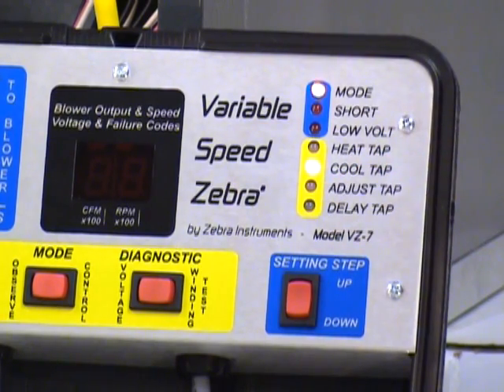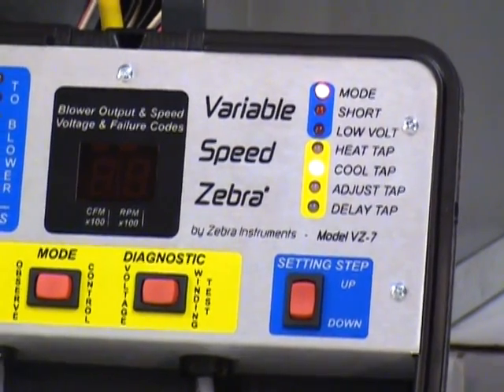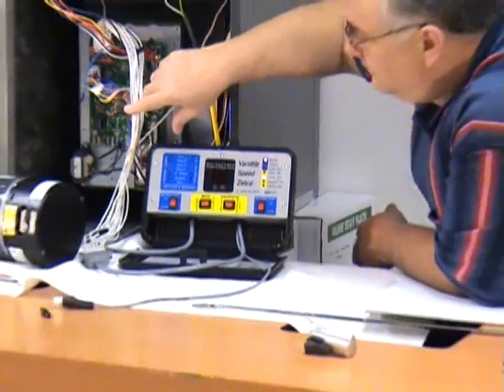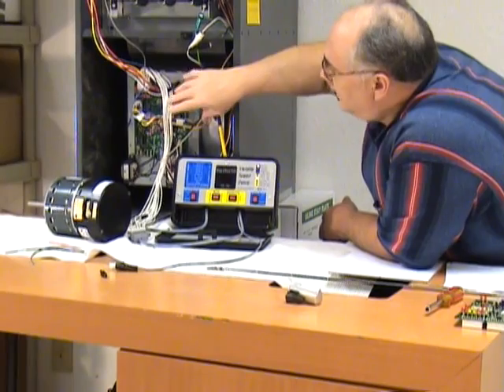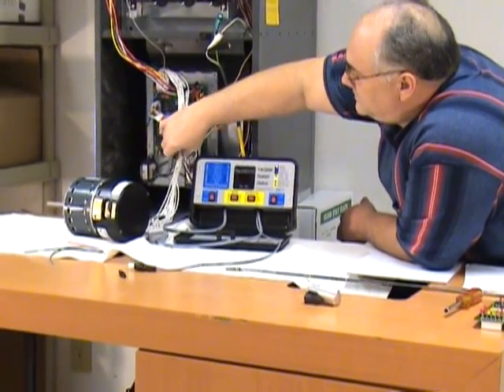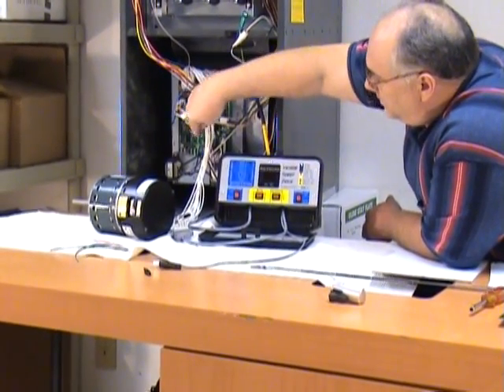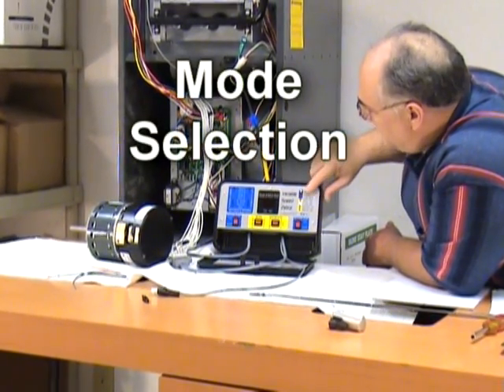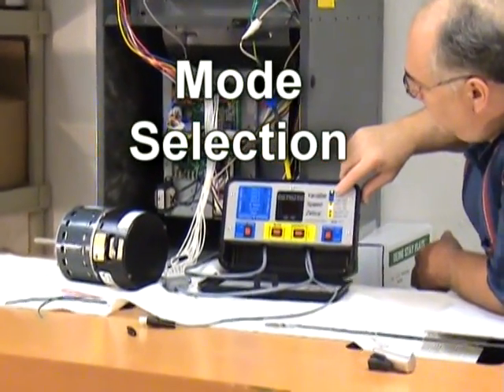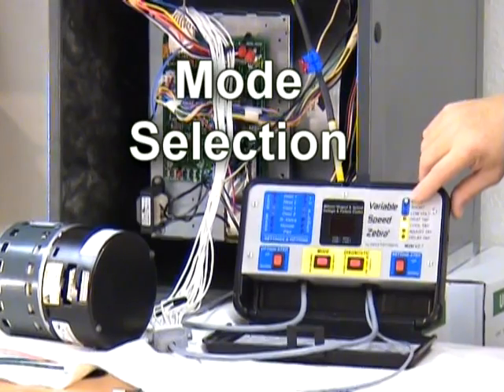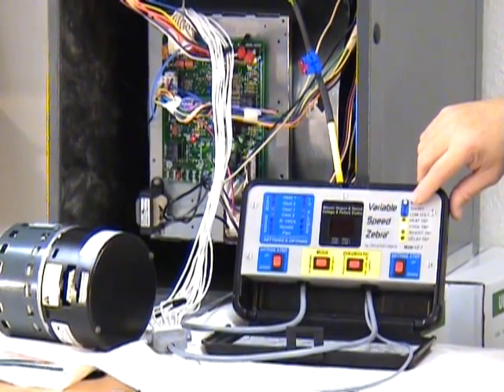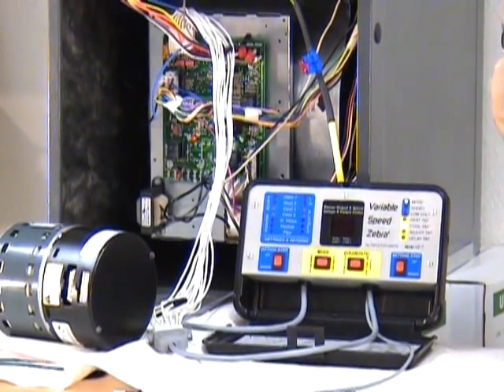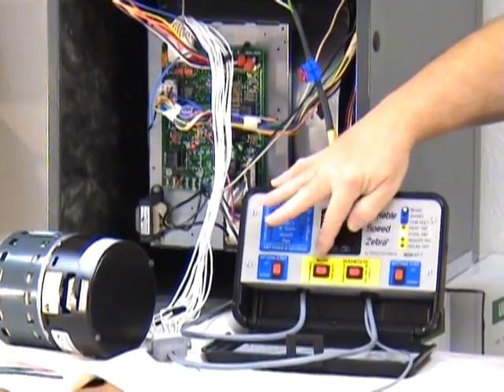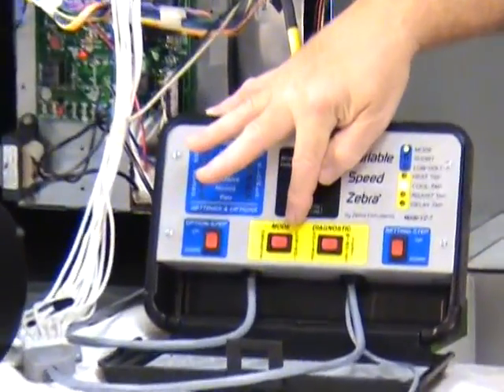So anyway, we're going back to what you do to start up. You've connected the variable speed Zebra in line, monitoring the signals from your board going to the motor. You don't see anything going on right now, but it's because this mode light is asking you to select a mode. We have two different modes that we can easily go into, and that's the observe mode and the control mode. I'll demonstrate the observe mode first.